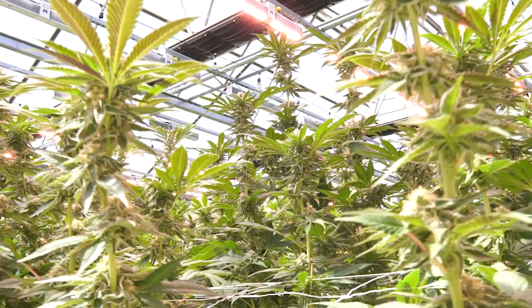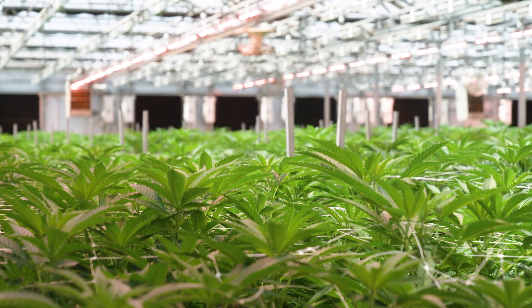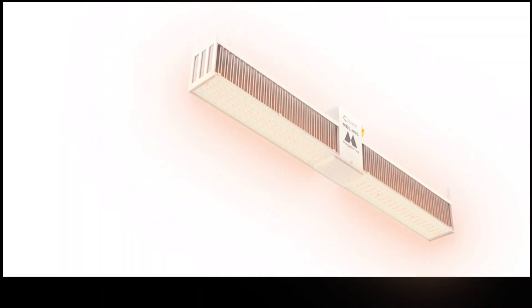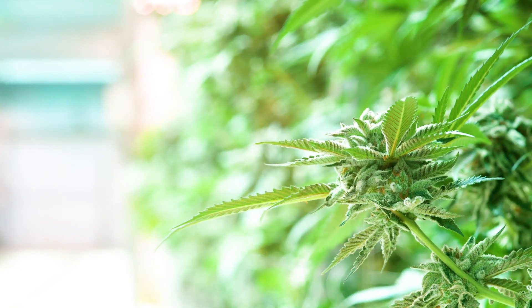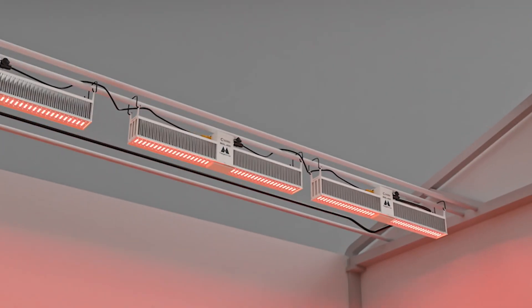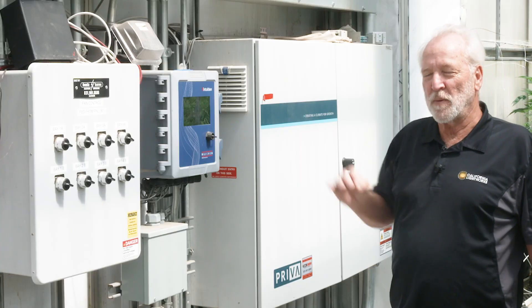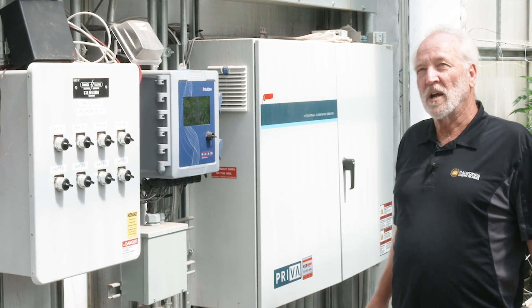This can take full advantage of all the options of the Mega Drive lighting system. You have zero to 10 dimming, from zero to 100 percent intensity. It has two channels — white on one channel, red on the other — so you can alter the spectrum control. You can use white as a view mode if you're working in the greenhouse and want to visually see the true colors of the plants. You can focus on the red channel, which is much more efficient and drives photosynthesis much heavier than the white channel. Using a photo sensor, you'd start with the red at lower light levels and eventually the white kicks in, giving you the most efficient photosynthesis out of the light spectrum automatically through the light sensor, the Priva system, and the two-channel lighting of the Mega Drive.